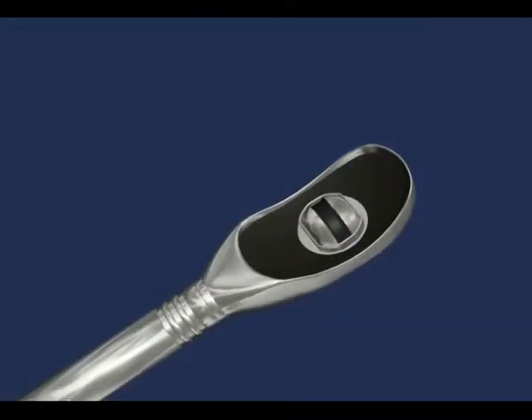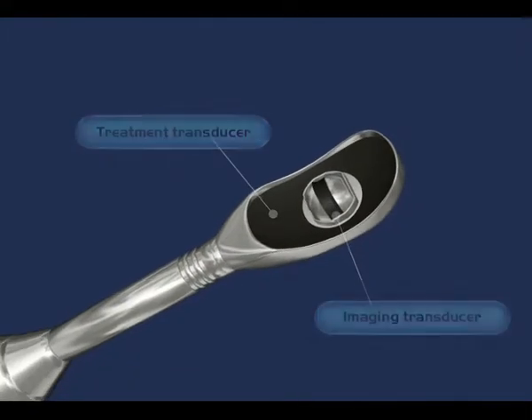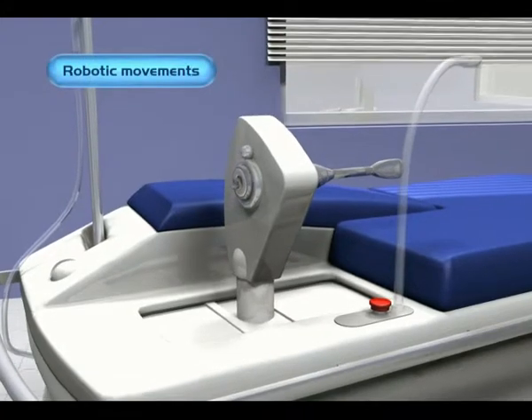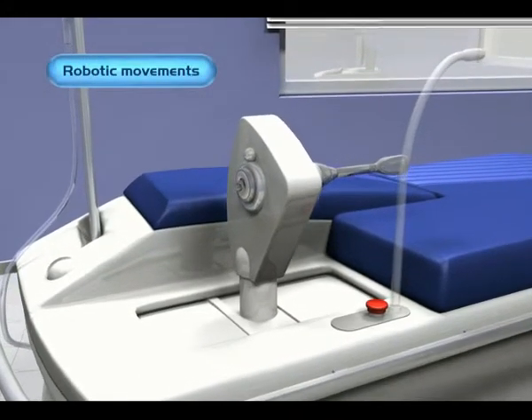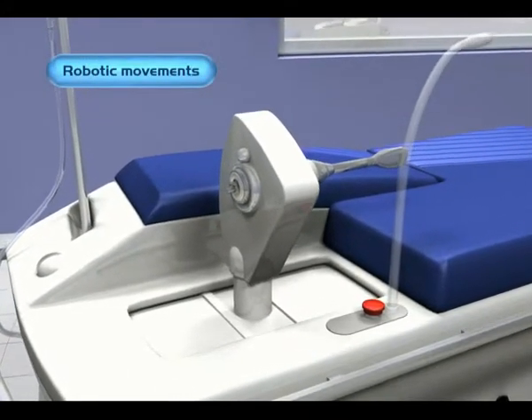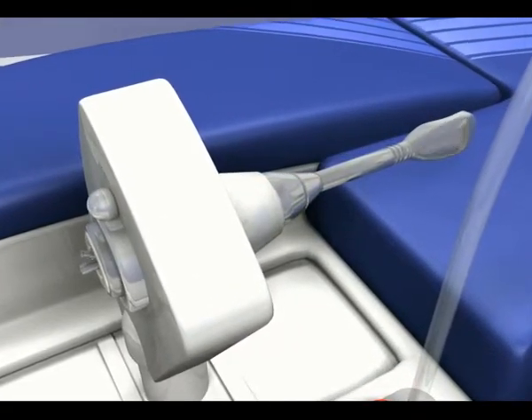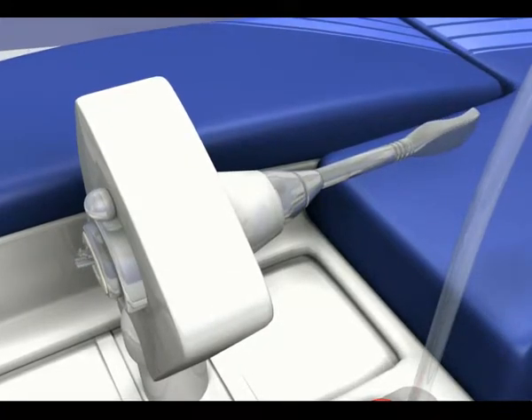The HIFU and the integrated ultrasound scanning transducers are located at the end of the probe. The probe's mobile support is an instrument with robotic movements which enable the device to move the probe automatically and extremely precisely during the procedure to ablate the targeted area within the prostate.